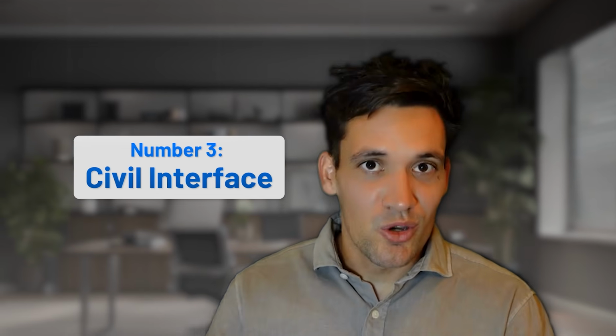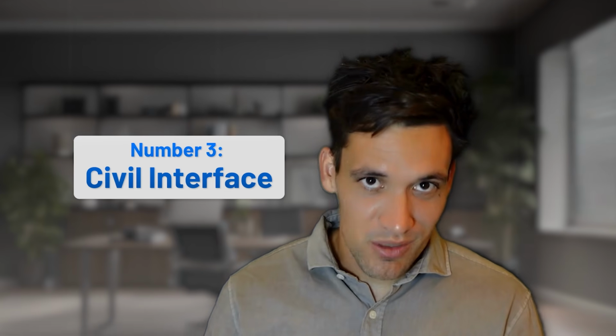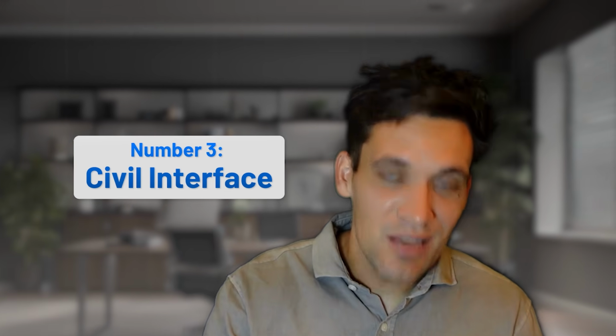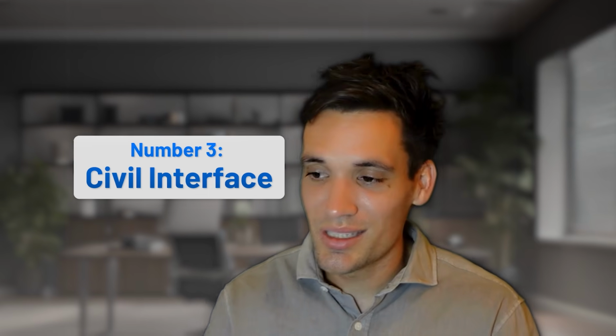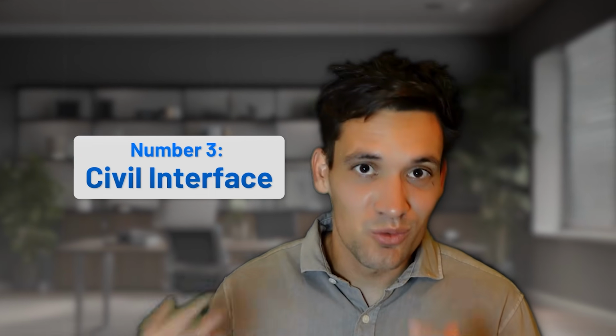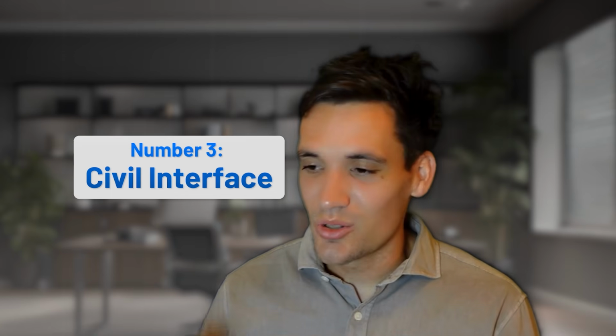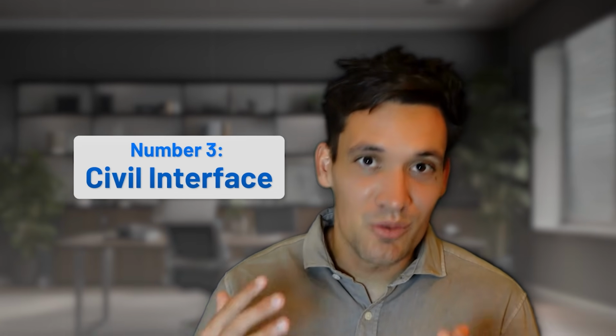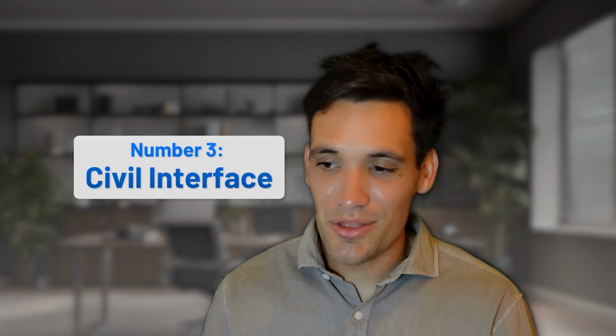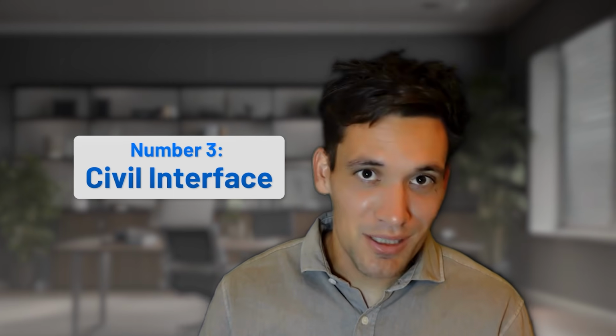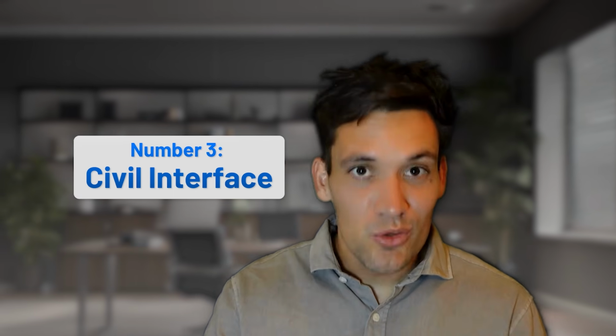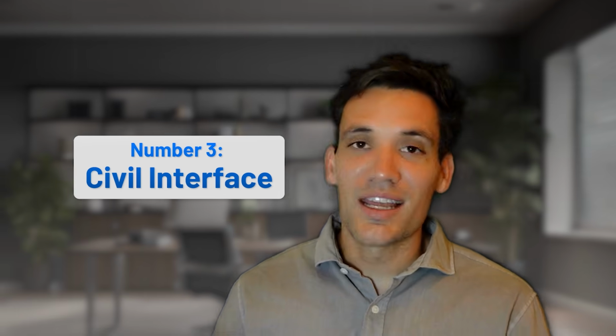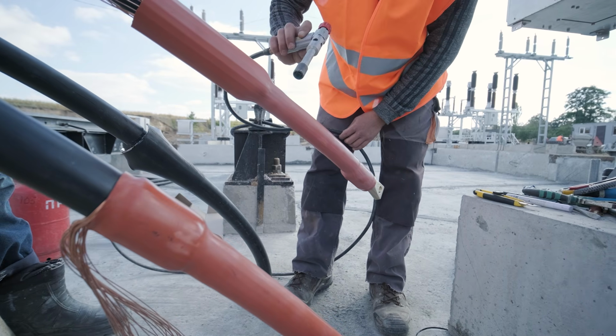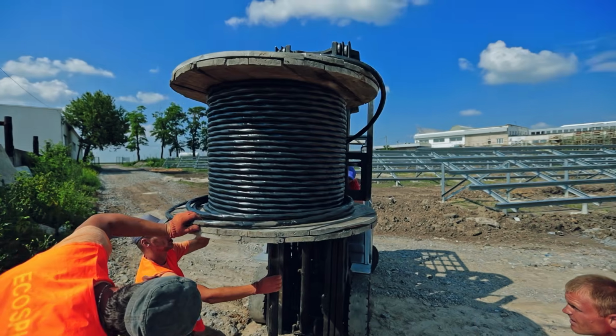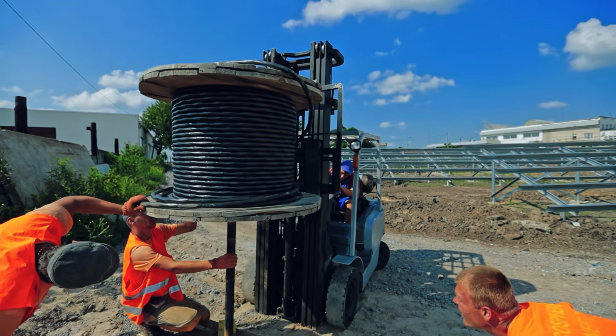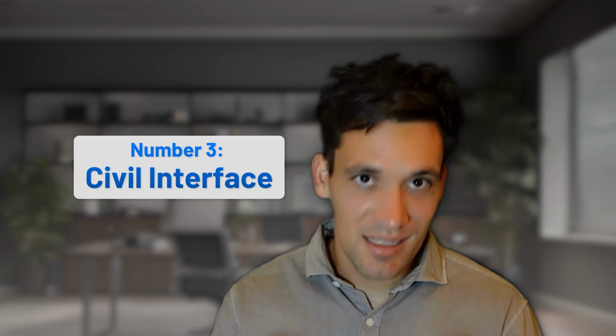You miss installing conduits through slabs that require expensive core drilling later. The wrong type and size of conduits get installed that either need to be changed or have rework done later. You get conduits that are crushed by reinforcement or filled with concrete during pours. And earthing electrodes quite regularly get completely forgotten. Now, the only solution I see to this problem is that you need an electrical team early, an electrical supervisor who's the one coordinating and doing this installation. Every time it's not the electrical team doing it, you end up with these exact problems.